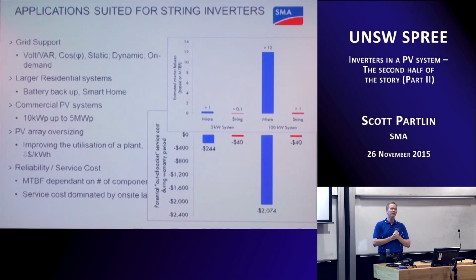Longer term life is something that we're concerned about as well, but for the purposes of this, it was just the warranty period. And what you see is that in this example, for both the 3 kilowatt and the 100 kilowatt systems, the string inverter statistically will have less than one failure throughout the warranty period. Now at the smaller system level, and you'll recall that was one of the applications where a microinverter is probably better suited, the difference between the micro and the string is neither here nor there. But as you move into the larger systems, the statistical likelihood of failure goes up proportionally with the number of PV modules deployed.